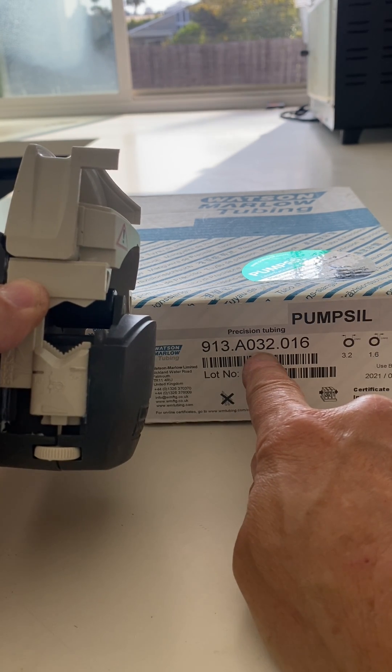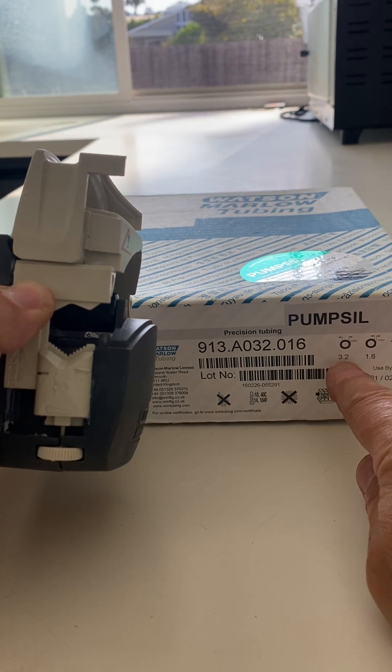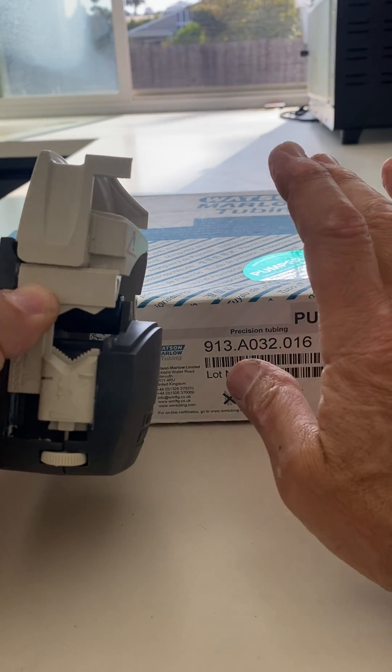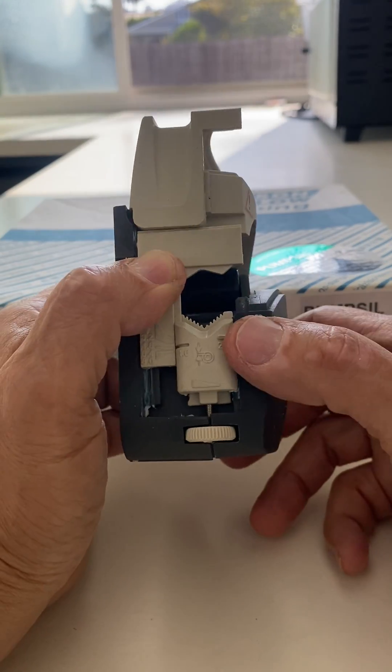So this tubing, for example, is 3.2 millimeters ID. It also tells you in a little graphic over here on the label.